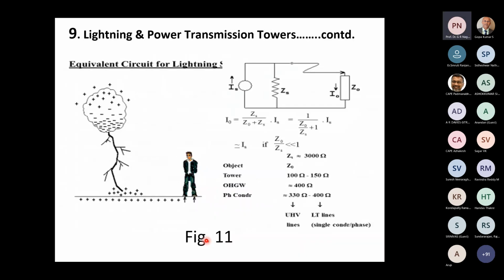Now, lightning can be represented by its equivalent circuit, which is a current source in parallel with its surge impedance. I'll not go into great detail. This is just for information. The object struck is represented by its own surge impedance, because in our case we are considering power line transmission towers. I have mentioned the values already: 100 to 150 ohms for towers, 400 ohms for ground conductors, 300 to 350 ohms for phase conductors. Typically, the surge impedance of the lightning channel is of the order of 1,500 to 3,000 ohms, but very often 3,000 ohms is considered.